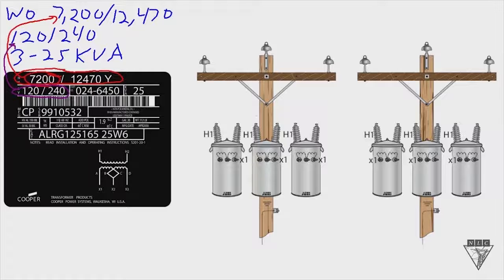And then the last part there is the size of the transformers. And right over here, what I'm circling right now, we've got 25 kVA is the size of our transformers, which matches on the work order, the 3 25 kVA transformers. So there's the first 3 things we need. The circuit voltage matches on the transformer voltage rating. Then the service voltage is a match, and the size of the transformers is a match.